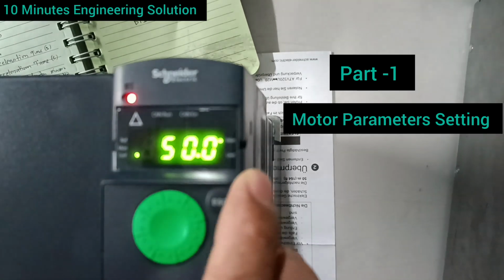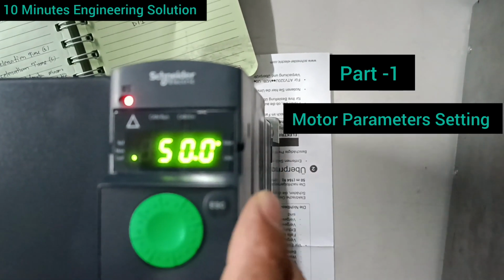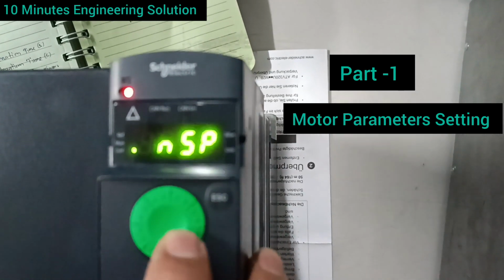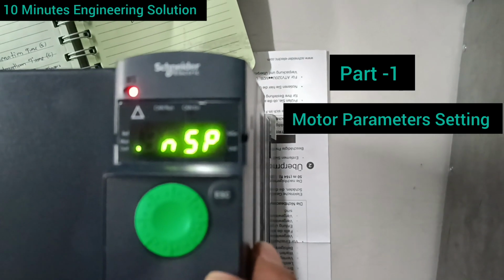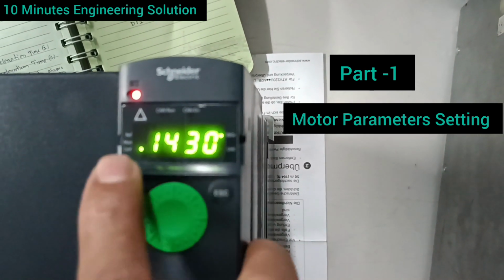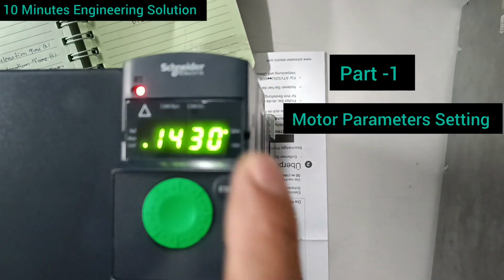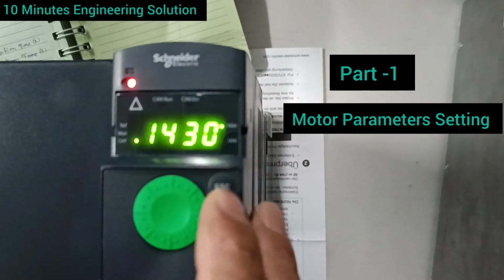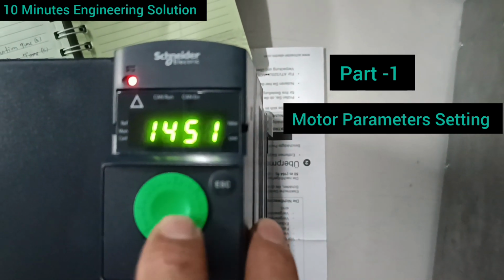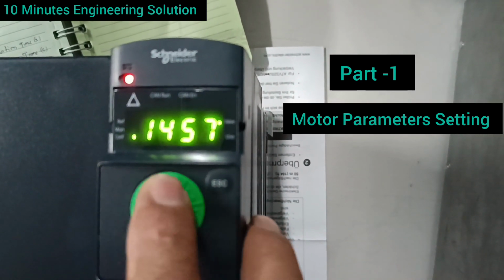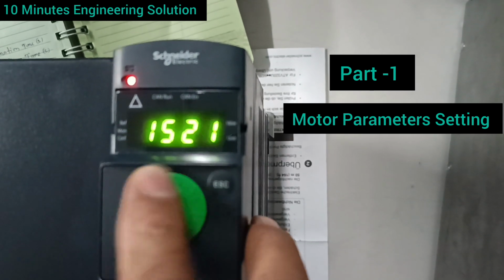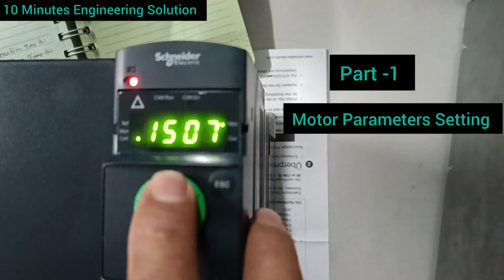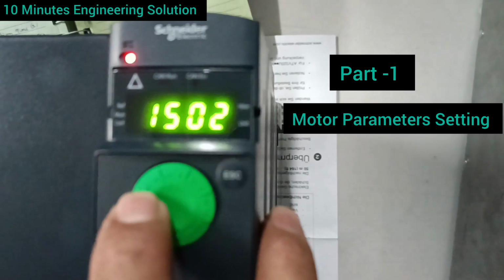FRS, the rated motor frequency as per the nameplate of the motor. And the NSP, the rated motor speed. I found my motor has a speed of 1500, so I'm setting the value 1500 for the rated motor speed.